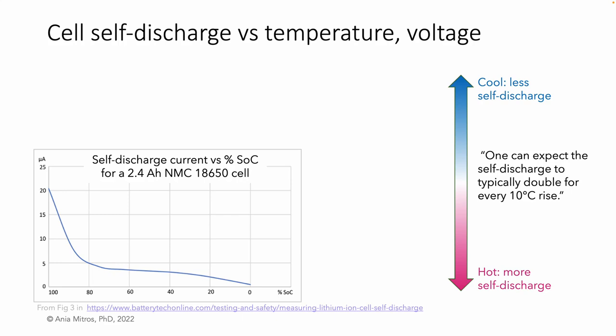I told you that temperature gradients cause imbalance since self-discharge increases with temperature. It turns out self-discharge is also substantially higher at high state of charge than at low state of charge. This is kind of nice, in that a nearly empty battery depletes itself more slowly than a fully charged one. Here's a curve for one battery's self-discharge as a function of state of charge, and from the same source, an estimate of self-discharge with temperature.